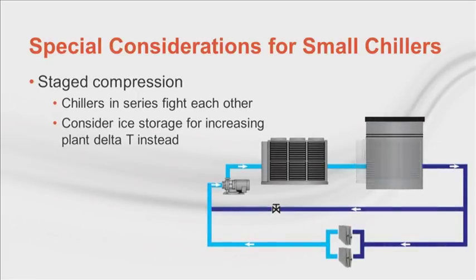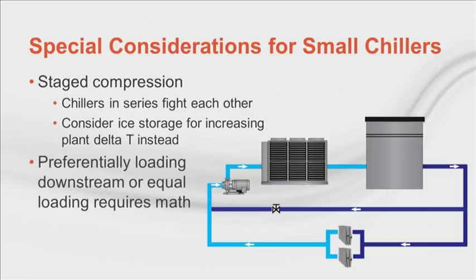Using ice storage gets us the benefits of series chillers and lower flow rates without having this problem. Now, there are certainly other advantages of thermal storage, as we discussed in depth in 2009. It's easy to preferentially load the upstream machine by giving it the same set point as the downstream machine. But to preferentially load the downstream machine, you must dynamically reset the upstream machine set point.